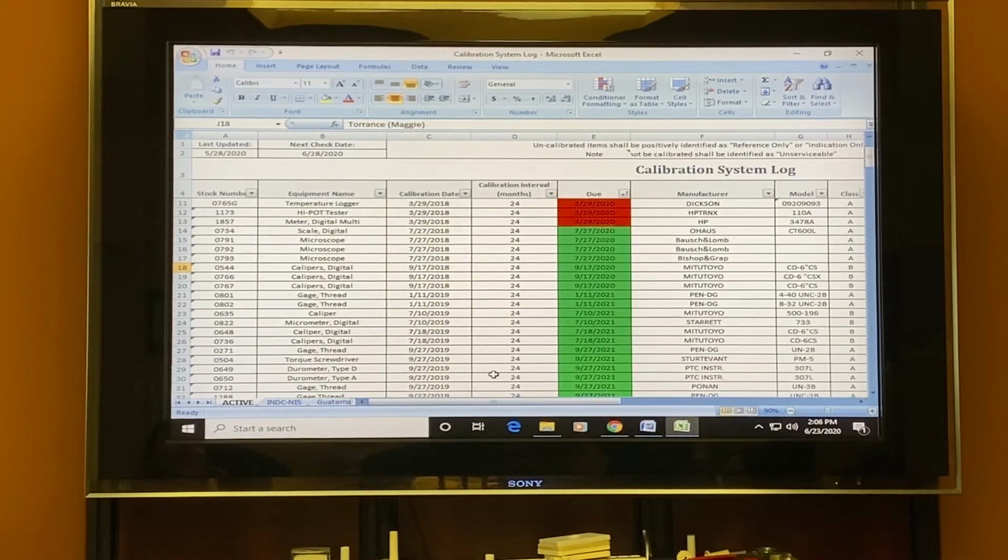Because there's a lot of back and forth on there, and sometimes they don't let me know. Like sometimes the items will be with Lorenzo because he needed them, so he asked for them. So that's why sometimes it's not marked that it's back here. We'll think that it's in Guatemala. But yeah, you can just walk around and ask. And even if it says Guatemala, just make sure, hey, I want to make sure this item's not here. And if Lorenzo says he doesn't have it, then you can go ahead and send an email to Guatemala and say, hey, this item is due for calibration. Can you ship it back to us? But you want to make sure you give yourself enough time.